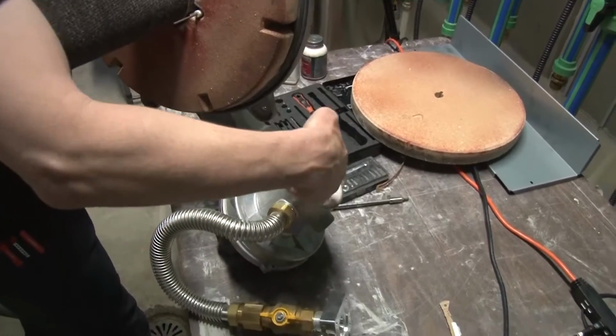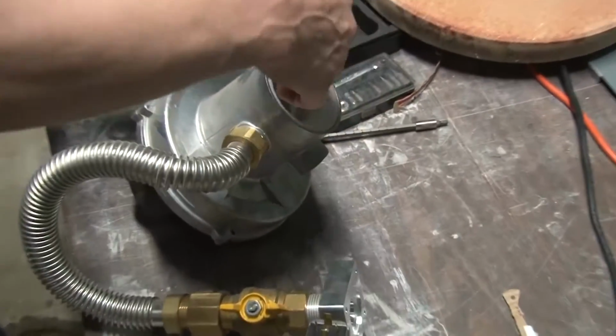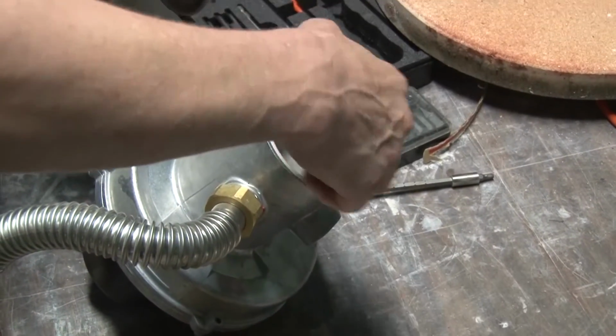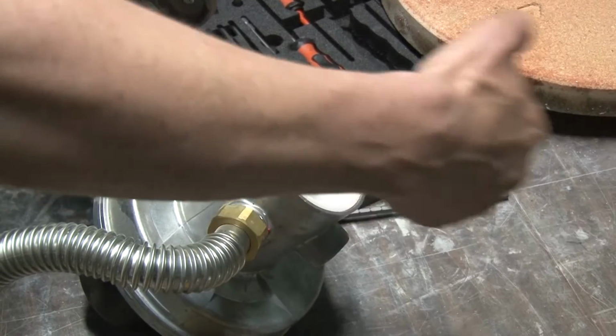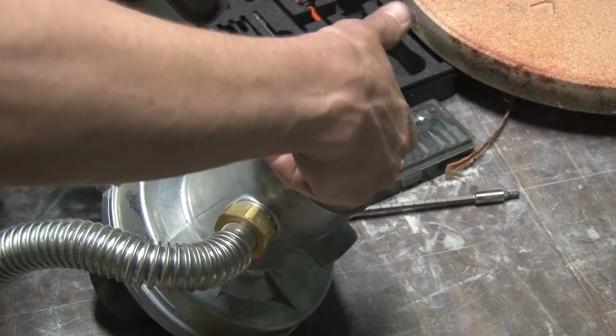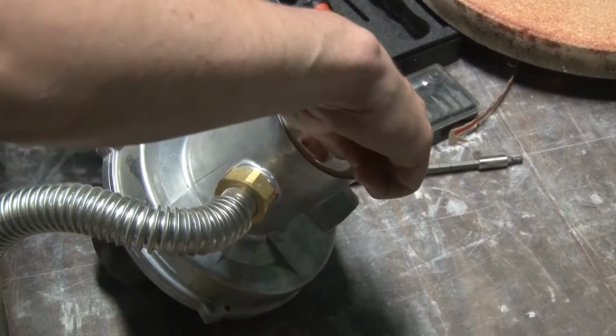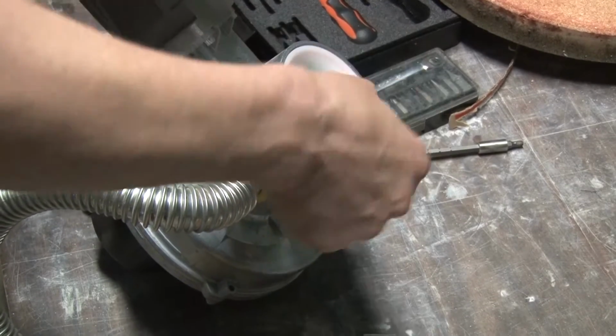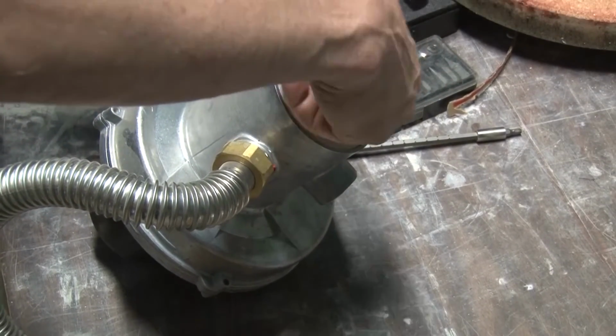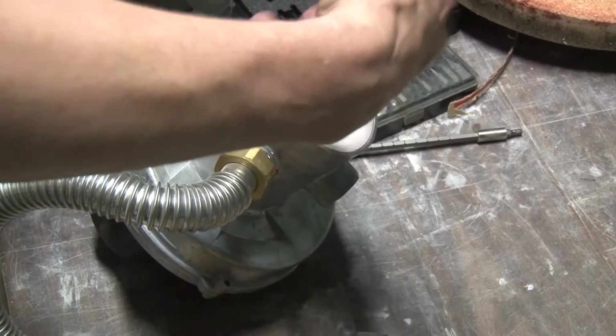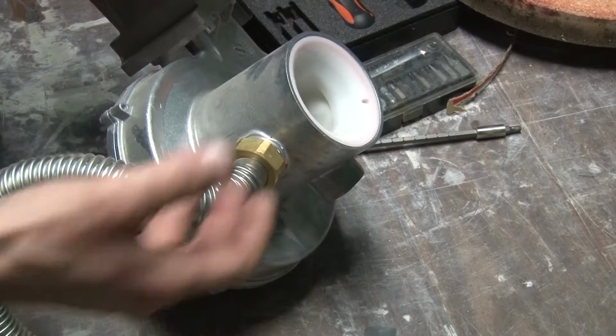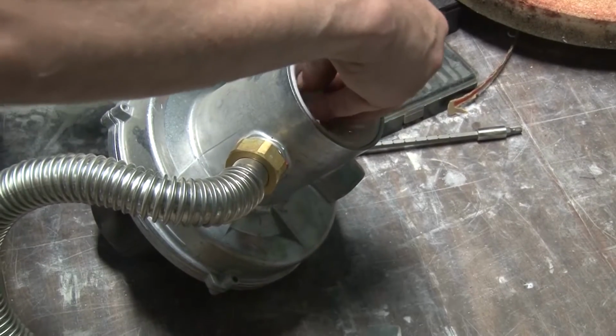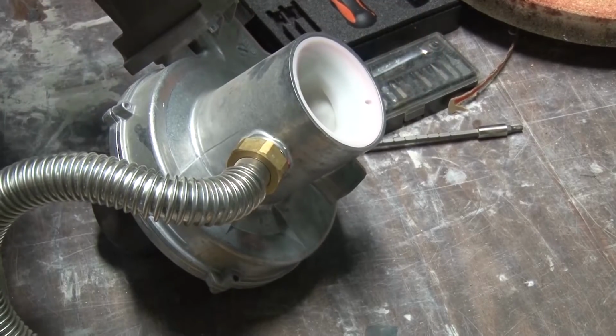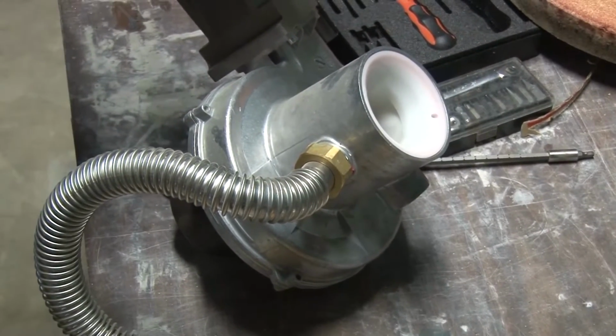It's the venturi of the boiler. We call this where the fuel and the air are actually meeting. This is the first spot that your combustion air is coming into the boiler, and of course your gas is coming through these little slots, just kind of the inside of that venturi. And this is where the air and the gas are entraining, they're blending. We call it a premix burner because everything is pre-mixing, fuel and air, before we actually get it to light off on the burner tube here.